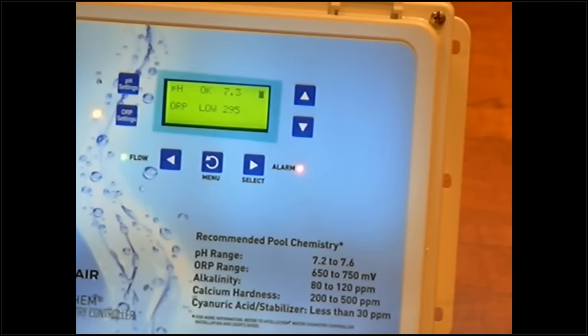For example, by having this unit, the saturation index will tell you if your water is corrosive, scaling, or ideal and normal. There's real benefit to having this, because right now you'd have no clue unless you took all the water samples you need to a company and asked what the saturation index is. With this unit, you just go to it, put in all the information, and it'll tell you exactly if your water is perfect and balanced, high and scaling, or low and corrosive.